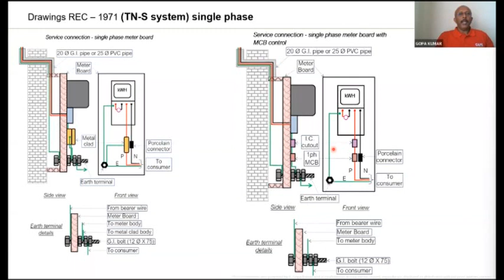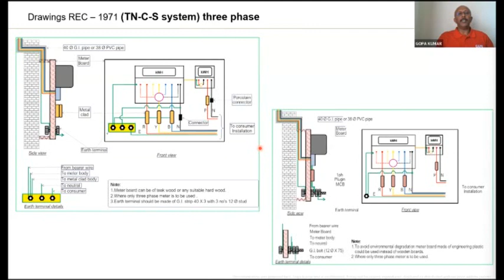Now, if we analyze all these documents, it is very clearly and explicitly written that the energy supplier, that means the electricity utility company, is supposed to provide either TNS supply or TNCS supply for a low voltage consumer. So that means the supply is something like this. Look at the first figure. This is called a TNS network. It means the energy supplier is supposed to give an earth terminal, an earth wire as well. But practically, they don't give this wire. They don't make this link.